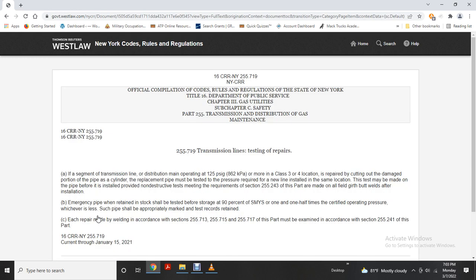Transmission line testing of repairs. A segment of transmission line or distribution main operating at 125 psi or more in a class 3 or 4 location repaired by cutting out the damaged portion of the pipe, the replacement pipe must be tested to the pressure required for a new line installed at the same location.